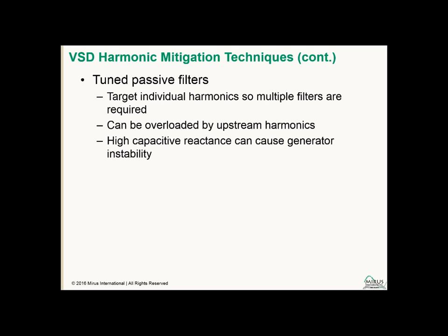Tuned passive filters have been used in the past. They're not that common anymore because of the problems that they've introduced. They typically would need to be tuned to each harmonic that you're targeting. So if you need a fifth harmonic being the most predominant, you'd need a fifth harmonic trap. But if all you do is filter the fifth, you're going to have high levels of seventh, so you'll need a seventh harmonic trap and so on.